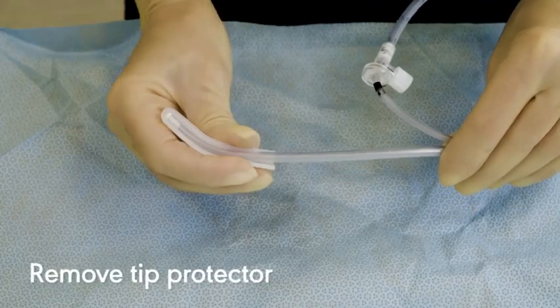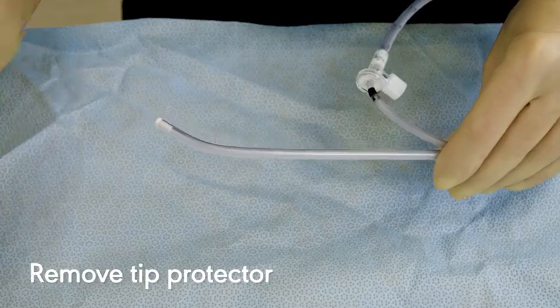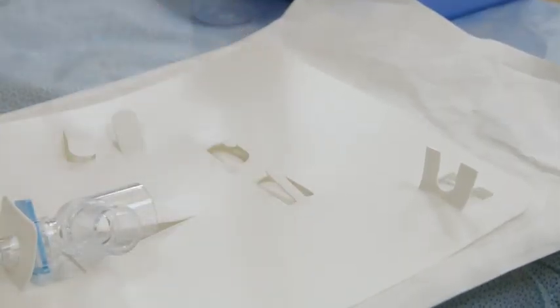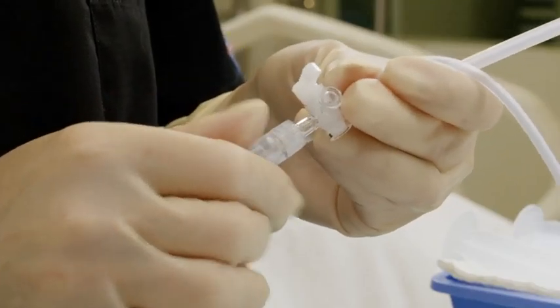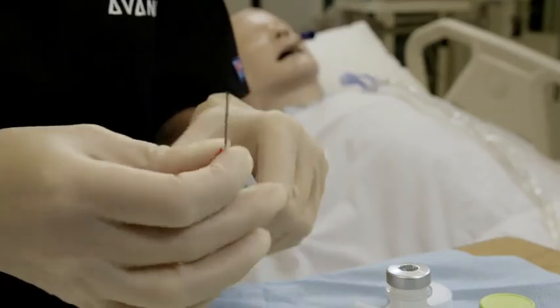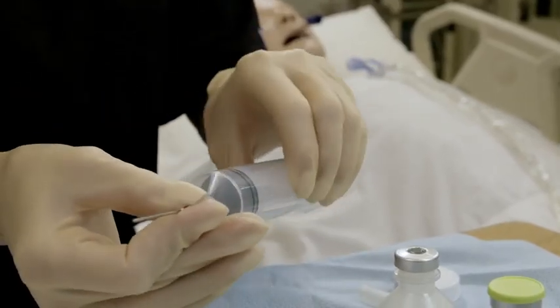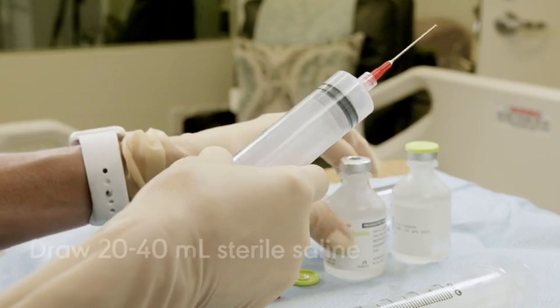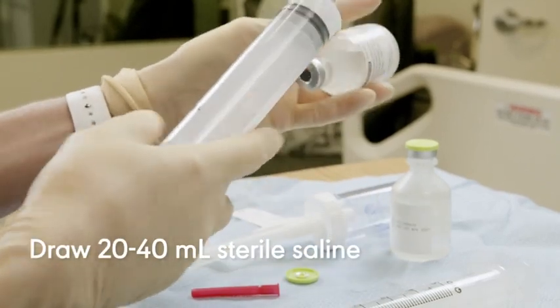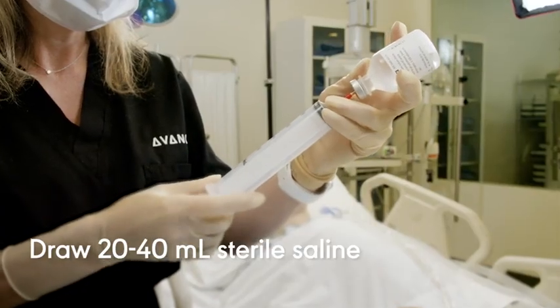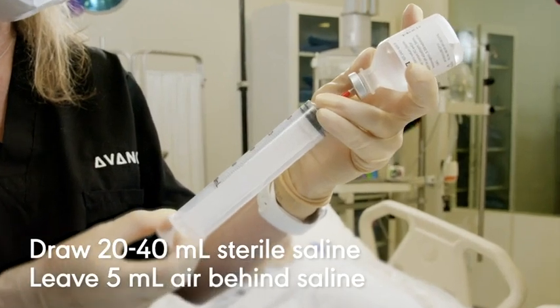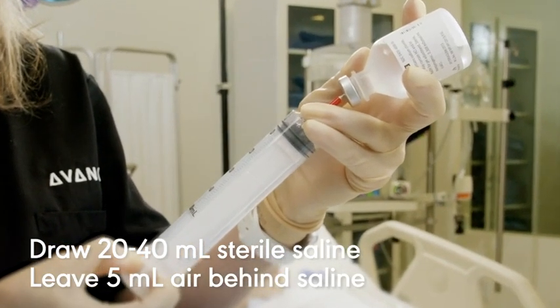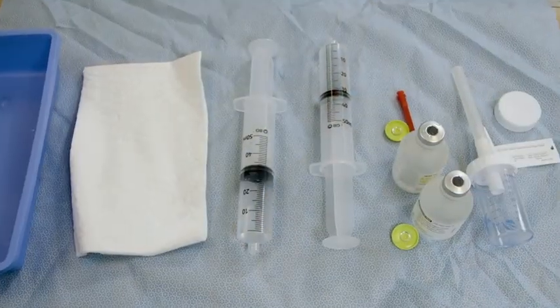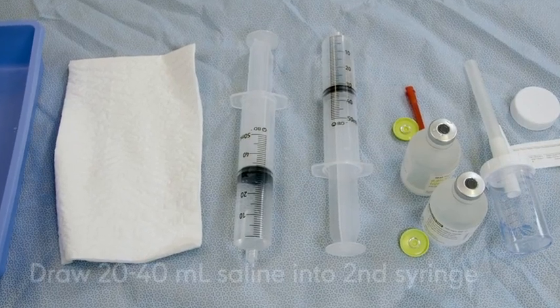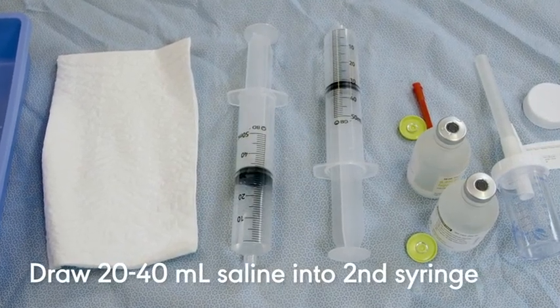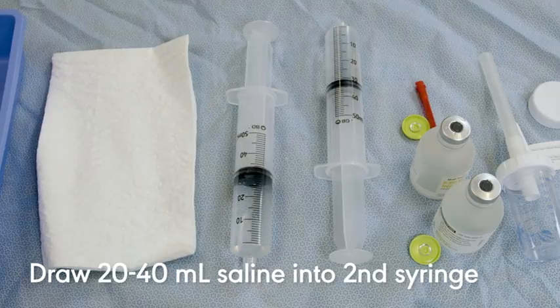Remove the white tip protector from the tip of the mini-BAL catheter. Attach the suction adapter to the distal end of the 3-way stopcock. Put the blunt tip needle on one of the syringes and draw 20 to 40 milliliters of sterile saline, according to facility protocol, into the syringe, leaving 5 milliliters of air behind the saline. Then, using the blunt tip needle, draw an additional 20 to 40 milliliters of saline into the second syringe.